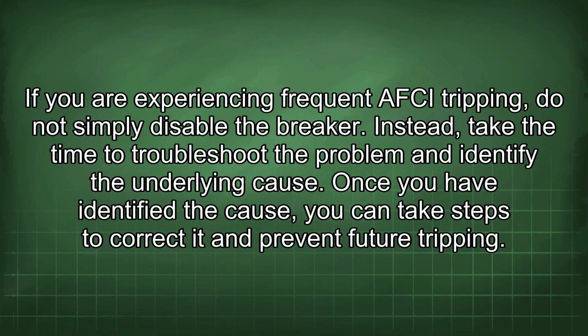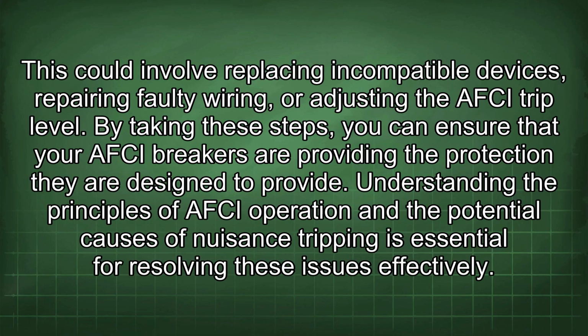Once you have identified the cause, you can take steps to correct it and prevent future tripping. This could involve replacing incompatible devices, repairing faulty wiring, or adjusting the AFCI trip level. By taking these steps, you can ensure that your AFCI breakers are providing the protection they are designed to provide. Understanding the principles of AFCI operation and the potential causes of nuisance tripping is essential for resolving these issues effectively.